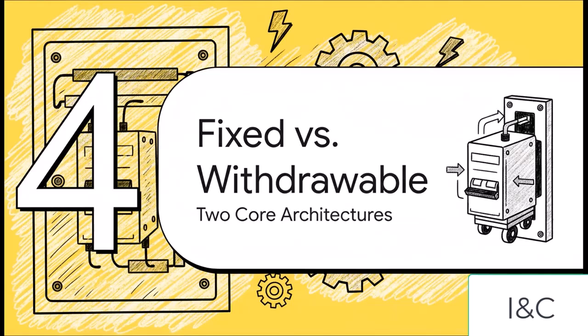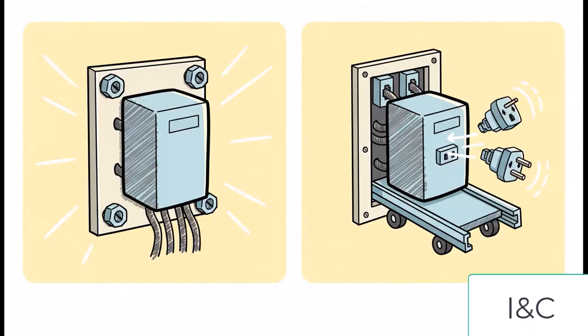Now let's pull back a bit. Beyond the internal workings, these breakers basically come in two main flavors. And believe me, the choice between them has huge practical implications. So on one hand, you've got the fixed type. And it's exactly what it sounds like. It's permanently bolted into the electrical panel, and its connections are all hardwired in place. But on the other hand, you've got the withdrawable type, which is really cleverly designed to just slide in and out of the panel on its own little chassis, using a kind of plug-in system for all its power connections.